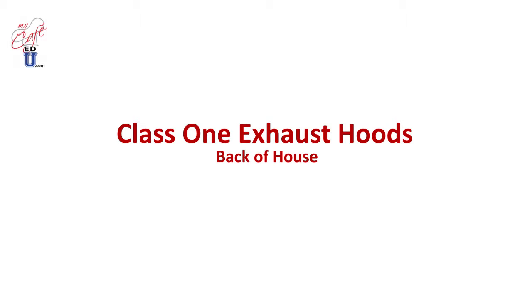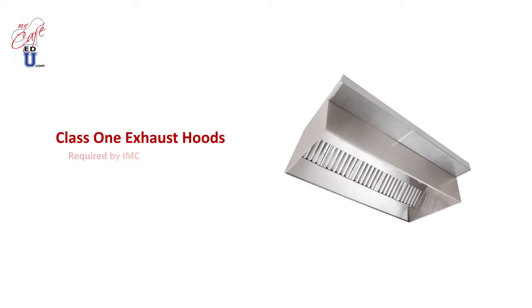Welcome to category number 1, Class 1 exhaust hoods, back of house. Today we'll be learning about the use and function of Class 1 hoods in a standard restaurant application. Class 1 exhaust hoods are required by the International Mechanical Code to be installed over cooking appliances that produce or emit smoke, heat, or grease-laden vapors such as ranges, fryers, grills, and charbroilers.